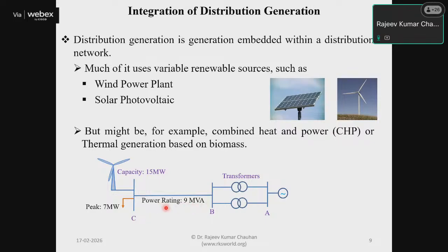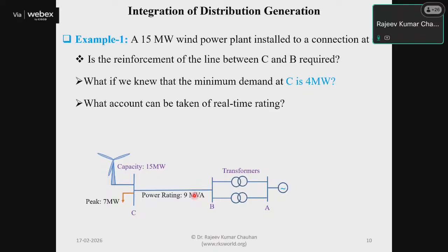So we need to manage the system. If we cut this load completely, the power generated from the wind power plant cannot be fed to the grid through this line because the line capacity is a bit low. So how can we manage all this? That's the challenge for the utility - to install the system with appropriate ratings.